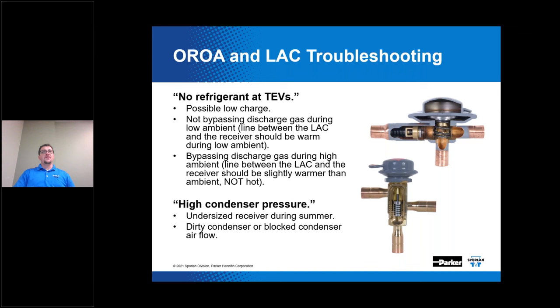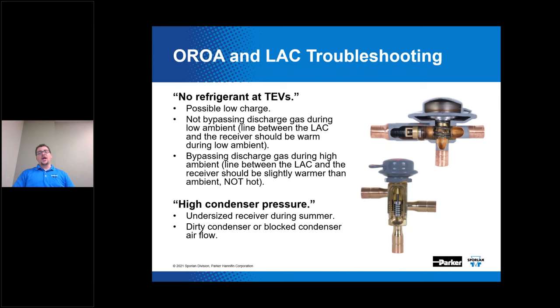Another complaint is high condenser pressure, which could indicate an undersized receiver during summer. Other causes include a dirty condenser or blocked condenser airflow. If the receiver is undersized, the technician will have to remove refrigerant every spring to prevent high head pressures, then add refrigerant back in the fall so the system contains enough refrigerant for flooding of the condenser. This adds an avoidable labor charge that would be eliminated with a properly sized receiver.